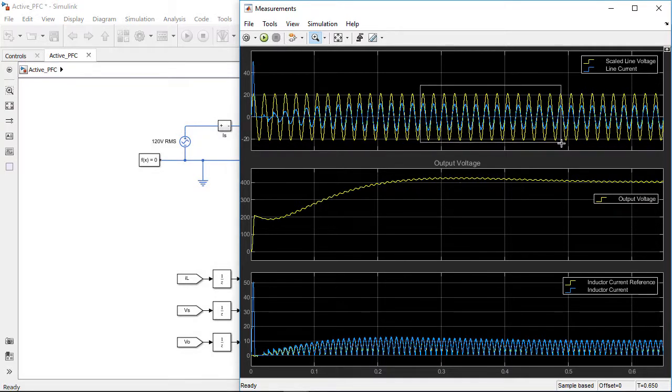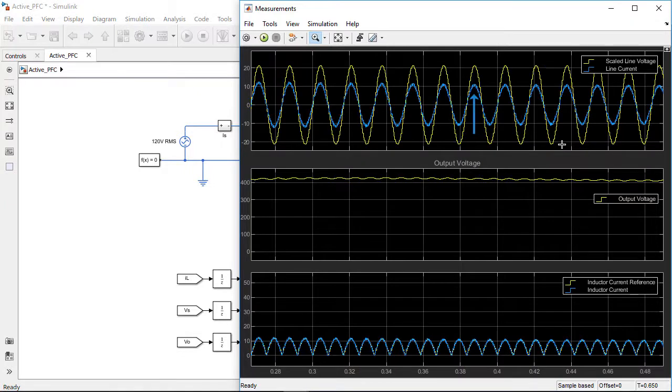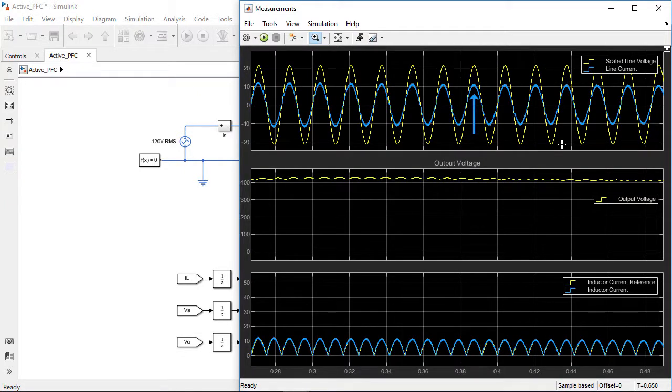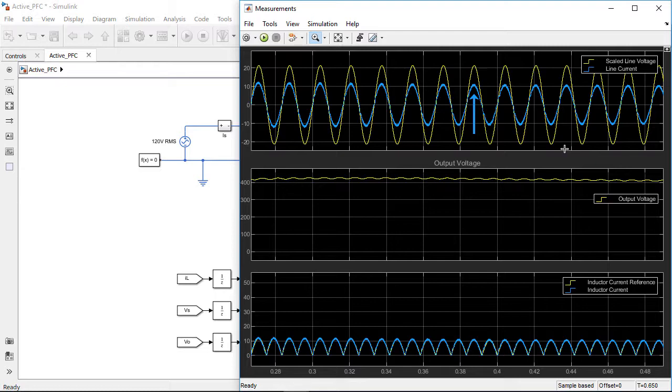The line current drawn from the AC grid resembles a perfect sinusoid and is much better than the current profile we had before the controller tuning. We see a reduction of harmonics, thus providing a better power factor.